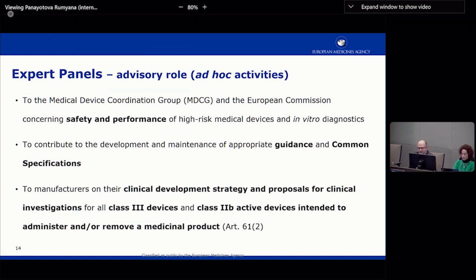Apart from mandatory activities, the expert panels have ad hoc activities in an advisory role. They advise member states through the Medical Device Coordination Group and the Commission on any issue regarding safety or performance of medical devices, contribute to guidance and common specifications, and can provide advice to manufacturers of Class III devices and Class IIB active devices intended to administer or remove a medicinal product — the same first part of Rule 12. Notably, the remit here is broader: it covers all Class III, not just implantable devices.